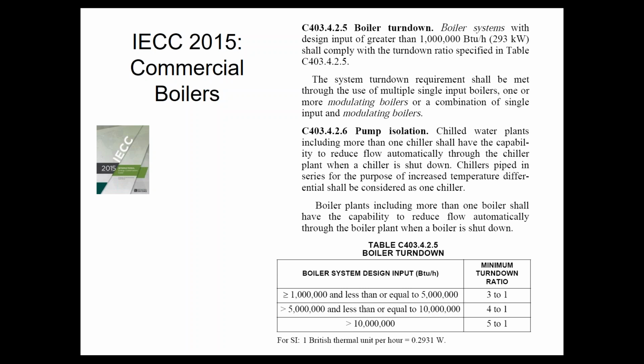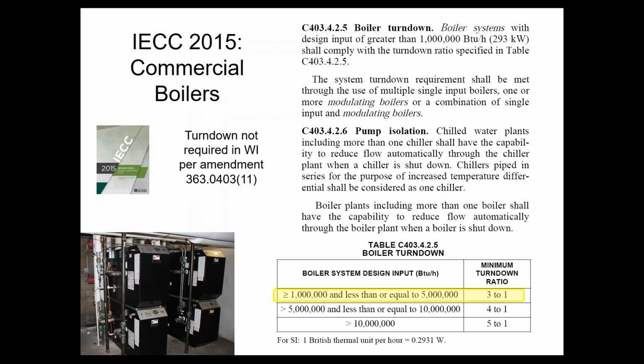You'd have to put in multiple smaller modular boilers, or you'd have to have a large boiler that has good turn down. For you guys in Wisconsin, Wisconsin made an amendment to not follow this turn down requirement. So in Wisconsin, you do not have to do this. Illinois or other IECC states, you would have to have this turn down. You also have to have other stuff for the hydronic plant. This is not really a change from prior years, but you have to have isolation on the pumps, right? So you're not flowing chilled water through a chiller that's not even running, that kind of thing.